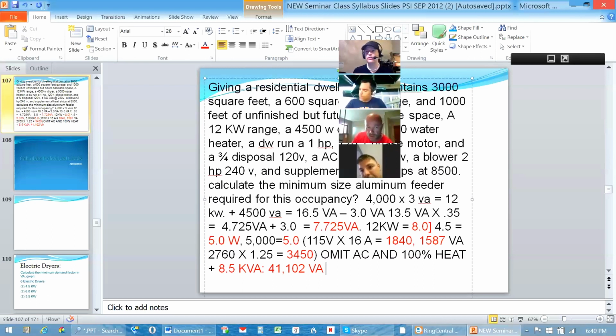That's just another additional step that you're going to have to remember to do on residential feeders, but it only applies to residential. So times that value times 0.83 in your calculator. Where'd that come from? It comes from 310.16B7 on page 160. Take a quick minute to read that and highlight it real quick if you don't mind. And coming from the service side, this is exactly how you want to calculate that. You would multiply it against your volt amps, or if you want to go ahead and divide it out by 240, so you've got your amperage values, and then times it times 0.83. Either way, you're going to get the same math. It doesn't matter. You're going to divide by 240 one way or the other. So I prefer to do it against the 41,100 volt amps so I can keep it straight.